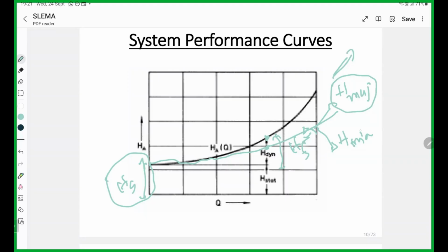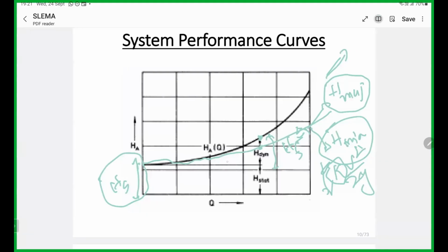Then for friction, if we think about the component minor losses, we can use radial bends and radial tees instead of the general bend. The k value, we have k v squared over 2g generally. Then this is the component loss. You have to select a component with less k value. Then we can save the friction head, optimize the pipe diameter, and save energy. This is one important thing in energy conservation in system head.